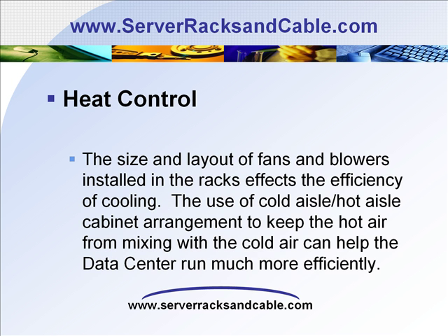Now heat control. Server rack cooling in the data center rack space depends on the number of switches and servers, as well as the arrangement of the rack mount server cabinet and cables. Too many copper cables in the floor can block the free flow of cooling air. The size and layout of fans and blowers installed in the racks affects the efficiency of cooling. The use of cold aisle and hot aisle cabinet arrangement to keep the hot air from mixing with the cold air can help the data center run much more efficiently. Details such as the watts per rack and the BTUs to be handled are important in the accurate design of the computer center so sufficient cooling is supplied.